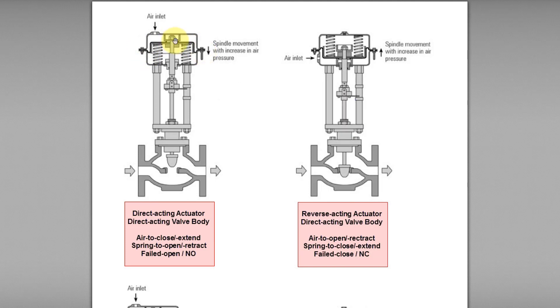How do we know if this actuator is direct acting or reverse acting? For a direct acting actuator, the air is applied to the upper portion of the actuator. If the pneumatic air is applied to the lower part of the actuator, it is called a reverse acting actuator.